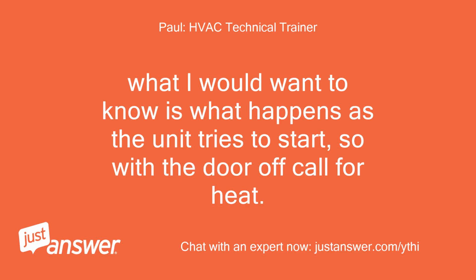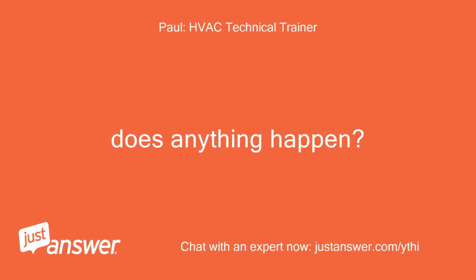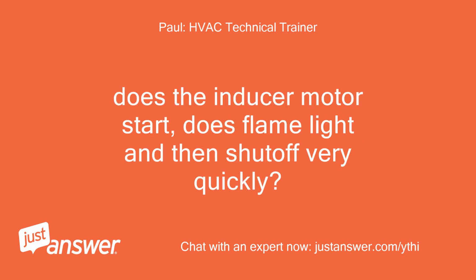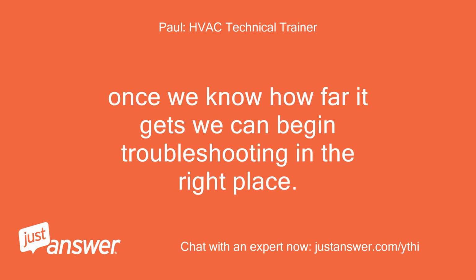What I would want to know is what happens as the unit tries to start, so with the door off, call for heat. Does anything happen? Does the inducer motor start? Does flame light and then shut off very quickly? Once we know how far it gets, we can begin troubleshooting in the right place.